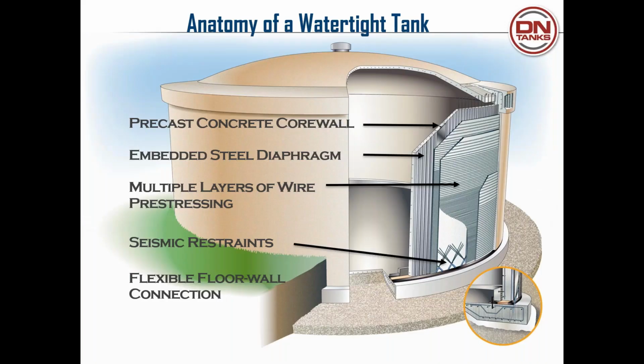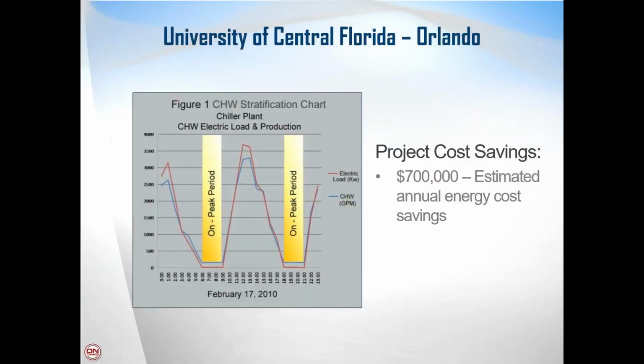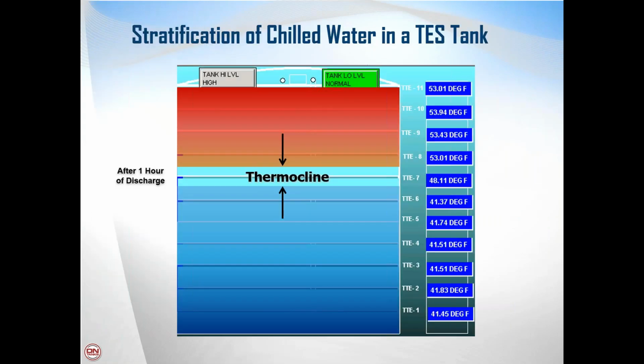Yeah, inside the tank, I'm trying to get back to my picture. Inside the tank, there are temperature sensors mounted vertically in the tank. So that's absolutely essential to keeping track of the amount of cold water and warm water in the tank. So those temperature sensors that are mounted vertically are important. And the only other sensor inside the tank is a level sensor. So there's a level sensor on the tank that is measuring the water depth. Even though this tank is part of the closed loop system, it is an atmospheric tank. So you're going to want to know the water level in the tank, because if there is a leak in their chilled water system out on the campus, the first warning that the owner will have is the water level in this tank is going to start to go down.